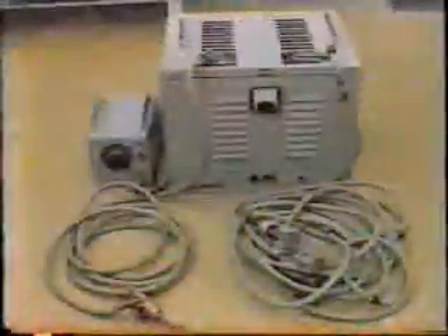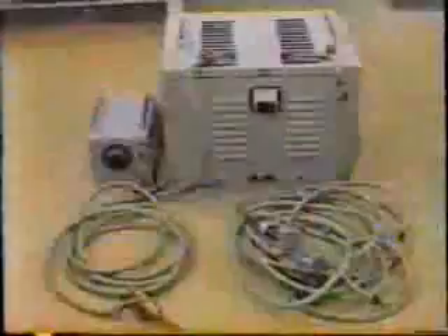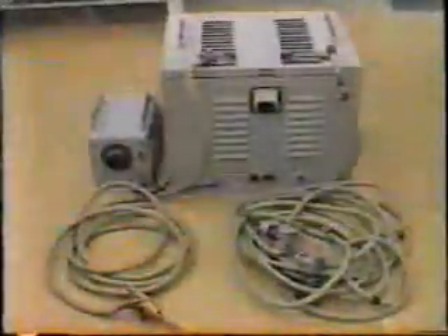Some companies use a larger test set in order to provide a higher value of primary test current, and so check operation of the relay itself in addition to verifying CT connections. Test sets may be rated up to, say, 10 kVA, with the capability of providing up to 1,000 amps at 10 volts.